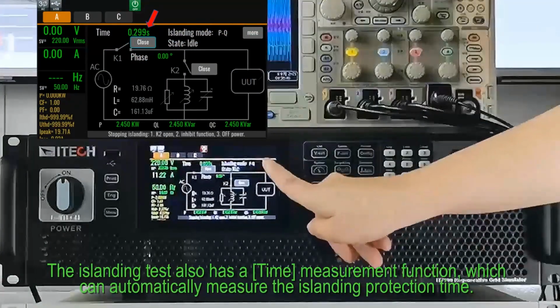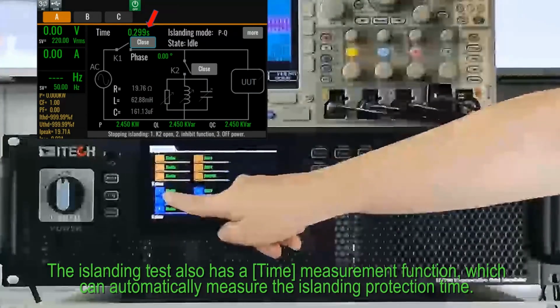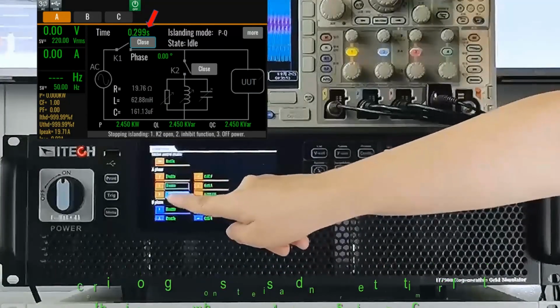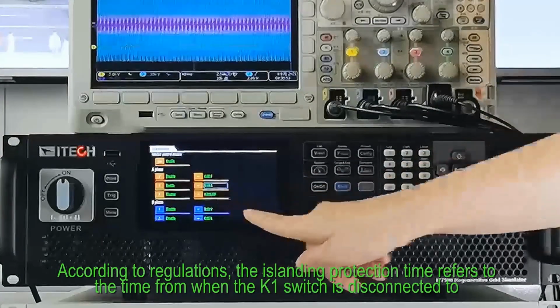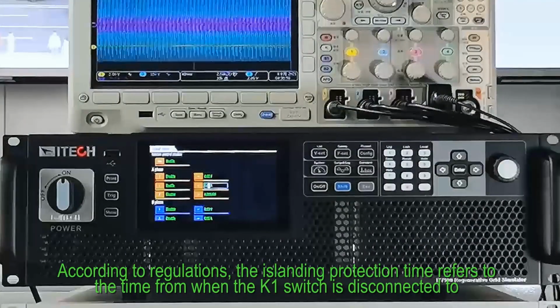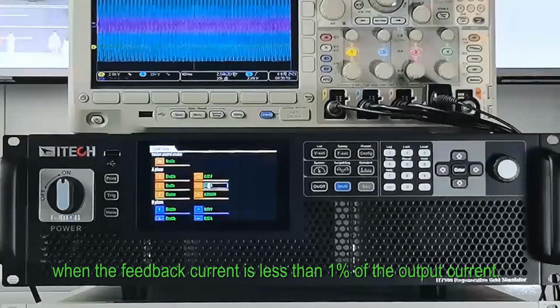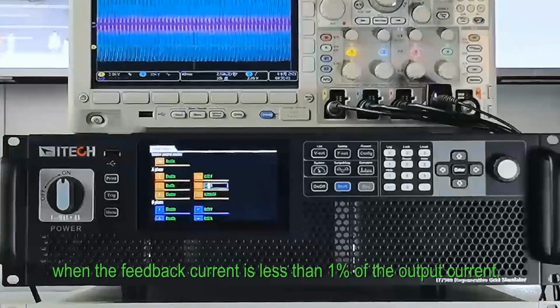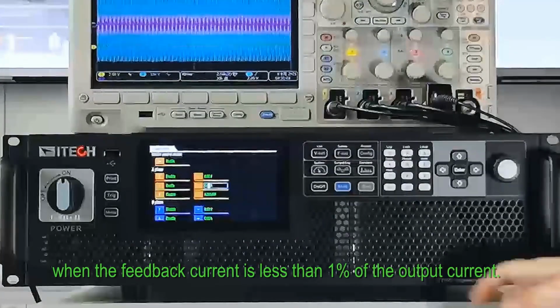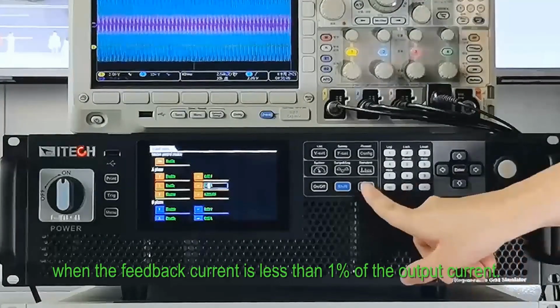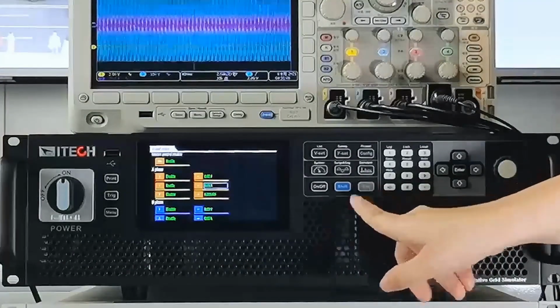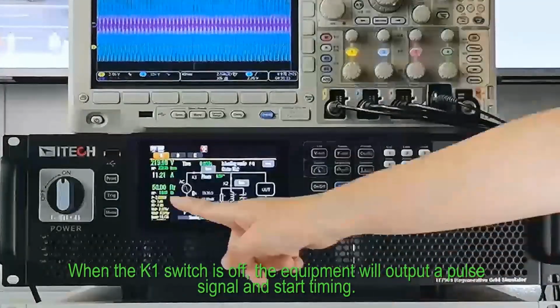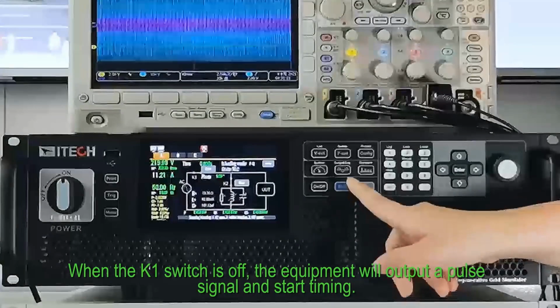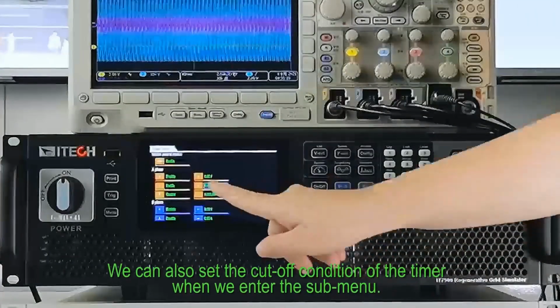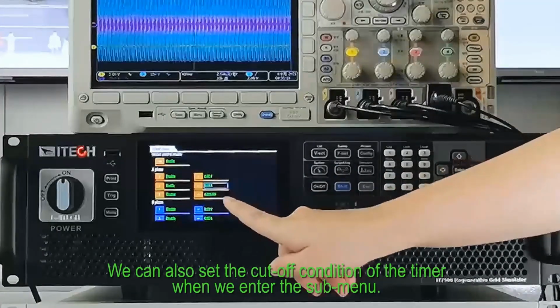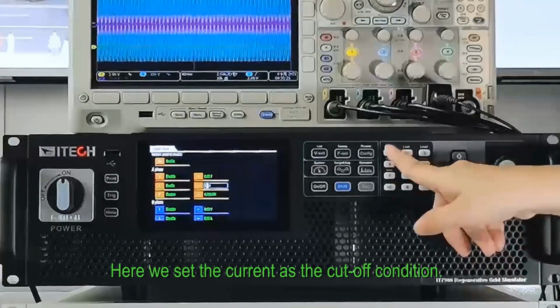The islanding test also has a time measurement function, which can automatically measure the islanding protection time. According to regulations, the islanding protection time refers to the time from when the K1 switch is disconnected to when the feedback current is less than 1% of the output current. When the K1 switch is off, the equipment will output a pulse signal and start timing. We can also set the cutoff condition of the timer when we enter the sub-menu.